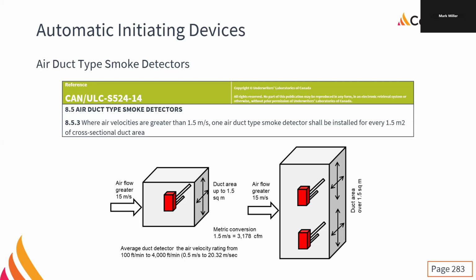But large facilities like colleges, universities, large apartment buildings, hospitals, they go for big air handling units because there's less maintenance. The air handling unit itself is bigger, but there's fewer of them. And so you could end up having to install a lot of duct smokes. I've done an air handling unit, this was a number of years ago, and if I had a picture of it, it's long gone. It was big enough that we had to put 8 duct smokes in the same spot to get enough coverage. It was ridiculous. Took a long time to install and wire, but it did look pretty cool one time.